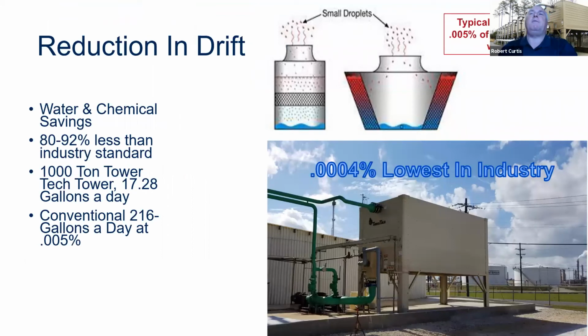I would be remiss, I feel like, if I don't at least mention this item because it is important. And we're winding down here in our presentation, but drift in a cooling tower used to not be a problem. But over the years, people have become more concerned about it due to Legionella, due to more equipment having failures because of water getting on that equipment. And one of the areas that people look at is, what is the drift rate of your tower? And traditionally, typically today, you see drift rates of 0.005% of the recirculating rate of water.